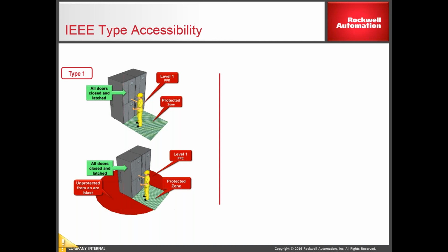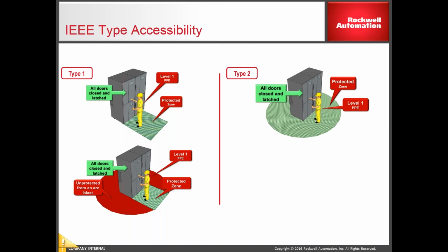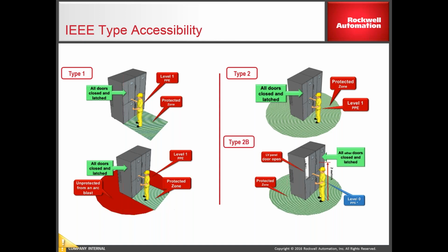So with Type 1 accessibility, if you're standing in the front of an ArcShield rated gear, then you're protected only in the front of that equipment, right? That's Type 1 accessibility. On the sides and in the rear, if you were standing in those areas and something happened, then you've got no protection in those areas on a Type 1 accessibility. Type 2 provides accessibility all around the equipment. So on the front, the sides, and the rear, you've got protection.